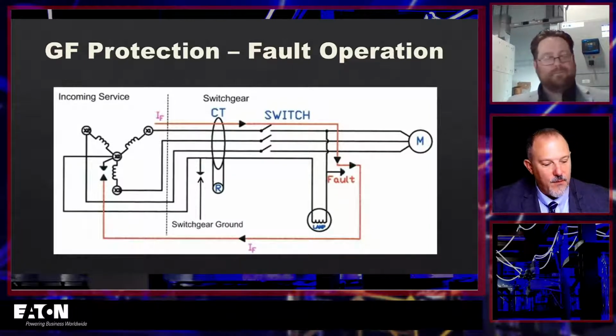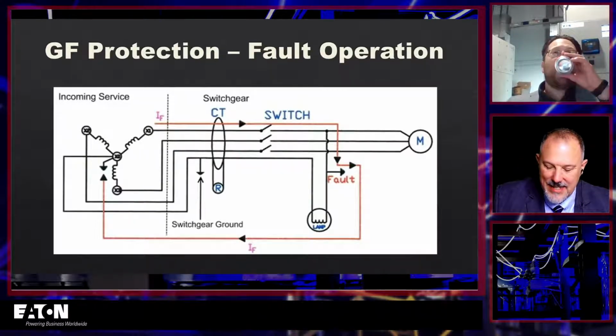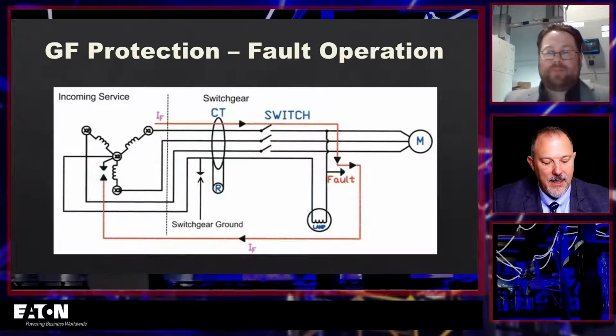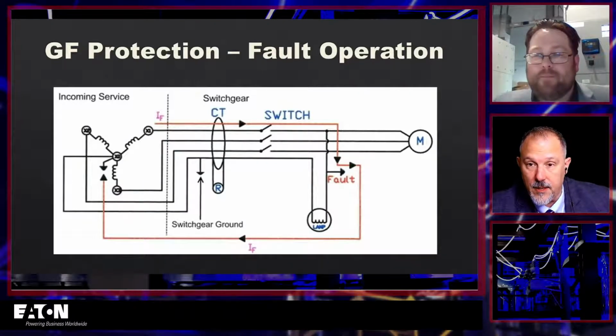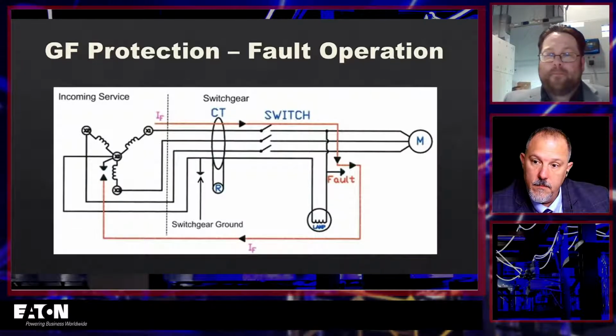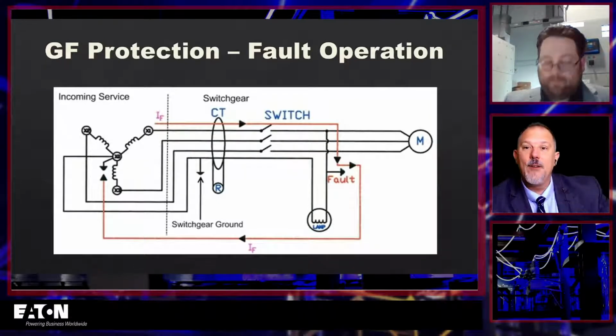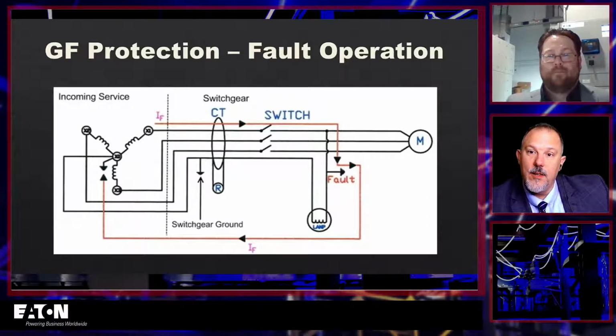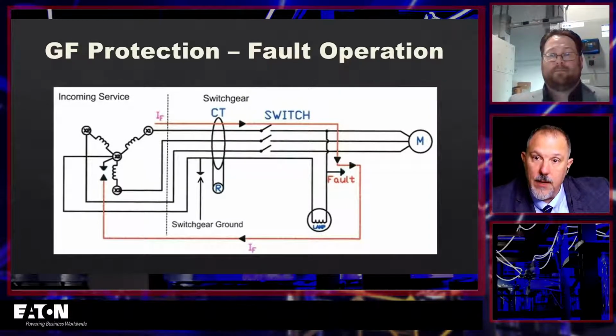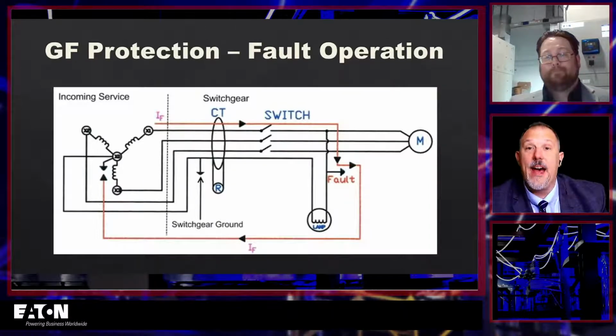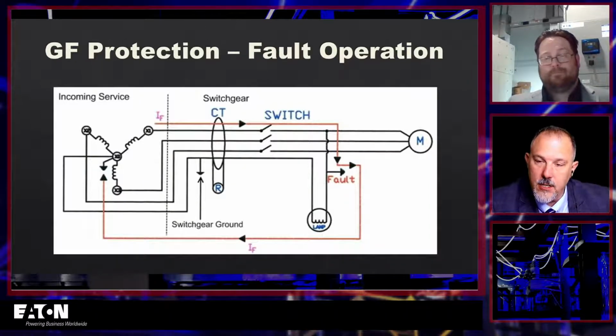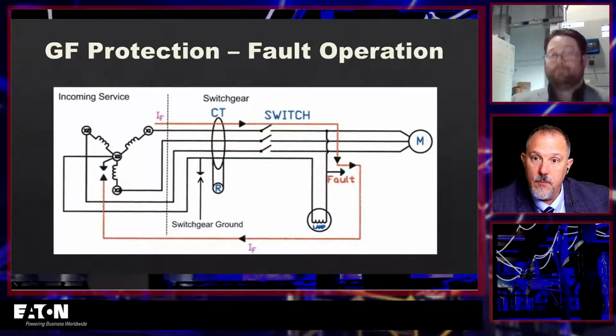So if you go to 250.4, and I know this is taking me down a different path, but I'll tell you what, this is something that I think goes with ground fault protection of equipment. If I provide ground fault protection of equipment closer to my load, I can take a fault off very fast. I will coordinate with that fault that's required, the ground fault requirements in 230, right, at the service. I can coordinate now with that and provide coordination, not do what happened to you in the cancer center, right? Yep.